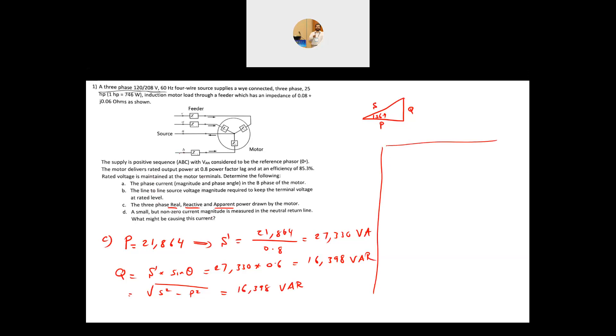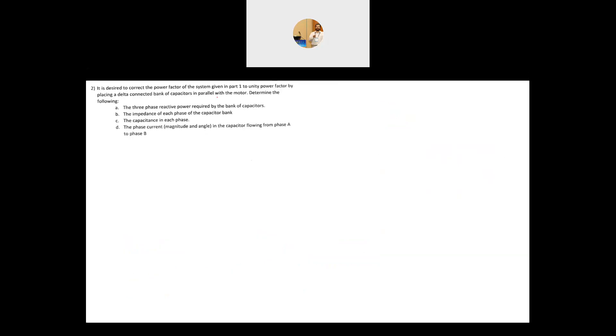There is a conceptual question: a small but non-zero current is measured in the neutral. For a purely balanced system, the neutral current would be zero. A small current exists because of imbalance among the three phases — specifically, the impedances Z_A, Z_B, and Z_C of the motor will not be exactly equal in practice, causing a slight imbalance. Imbalance in the supply voltages could be another reason.